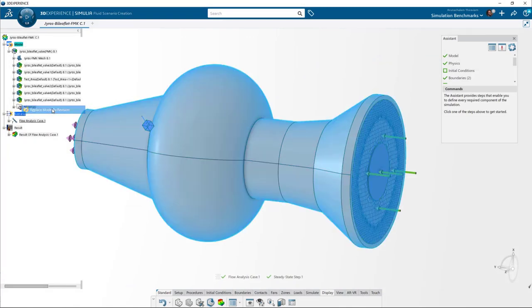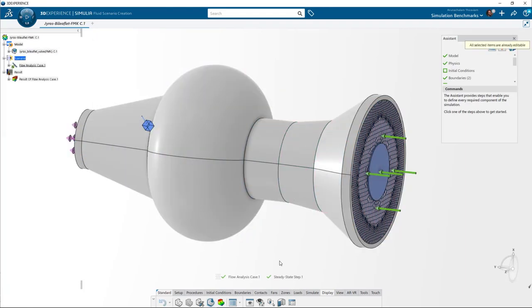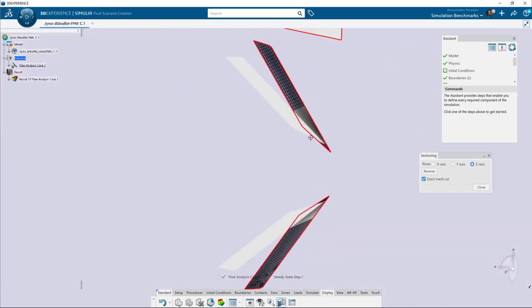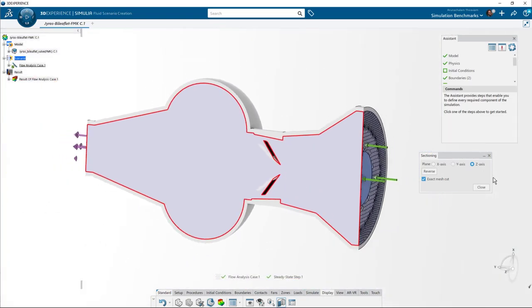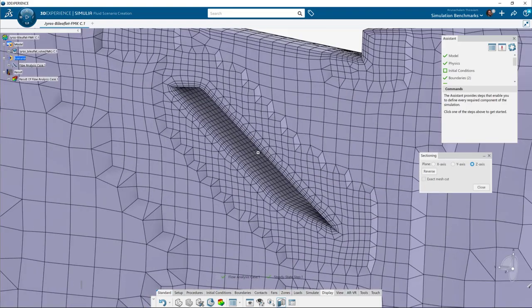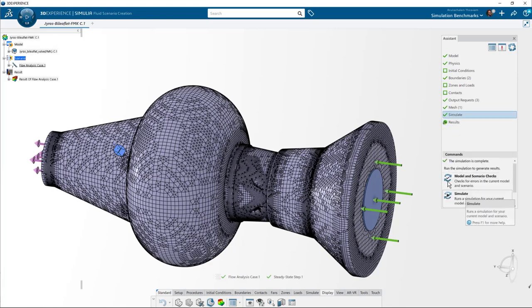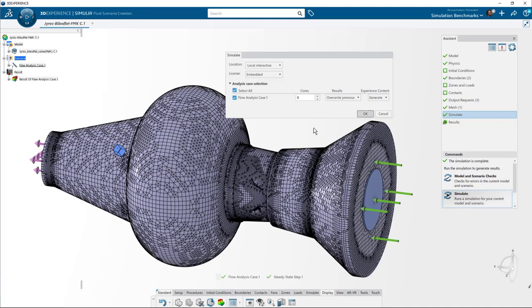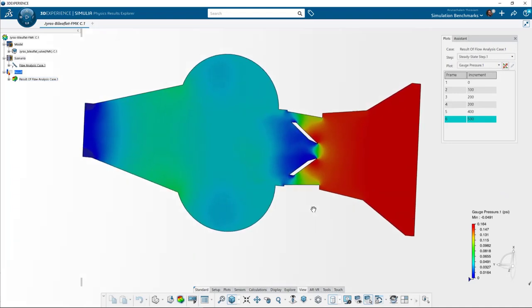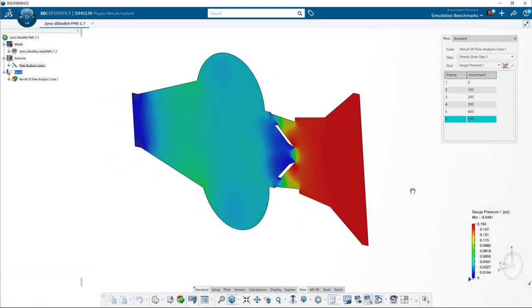Back in the 3D Experience platform, I'm able to replace the existing model with the new revision, so the simulation model updates with the new leaflet configuration. Once updated, I hit the update button and the software applies the automated mesh settings and local refinement around the leaflets to remesh the model with the new configuration. Since all the boundary conditions are automatically mapped, I can directly run the analysis and obtain simulation results for the new configuration — enabling generation of multiple design versions to study their efficacy.